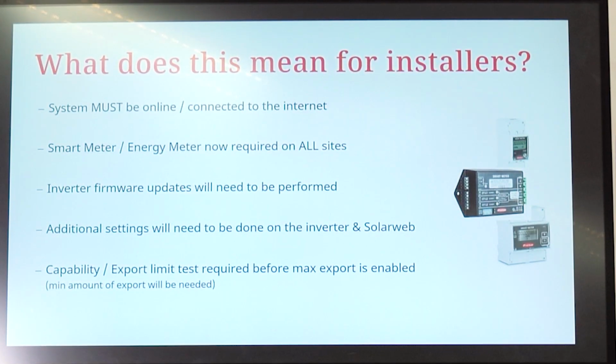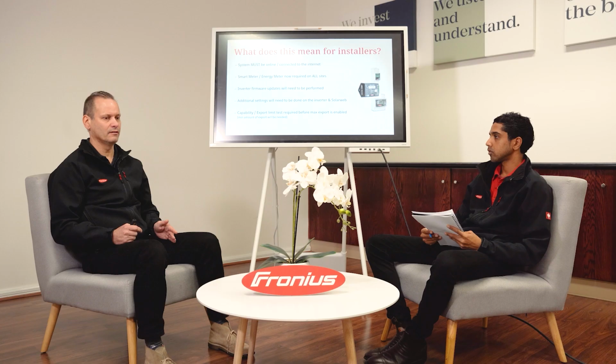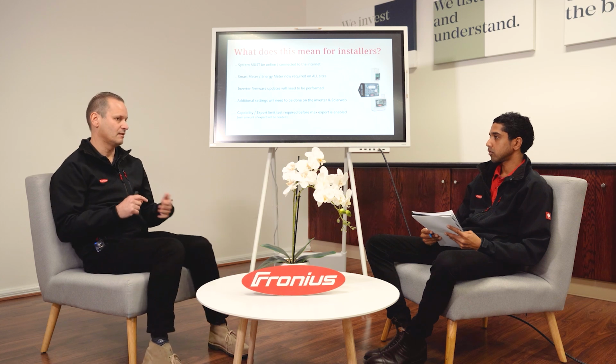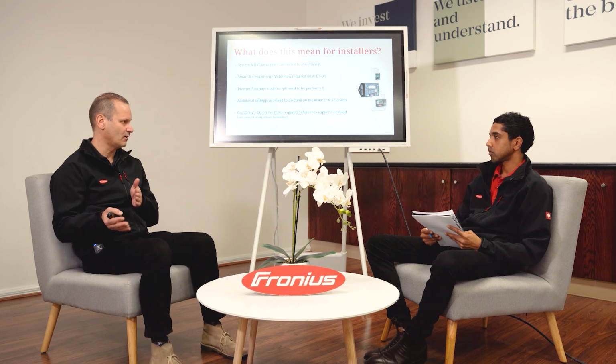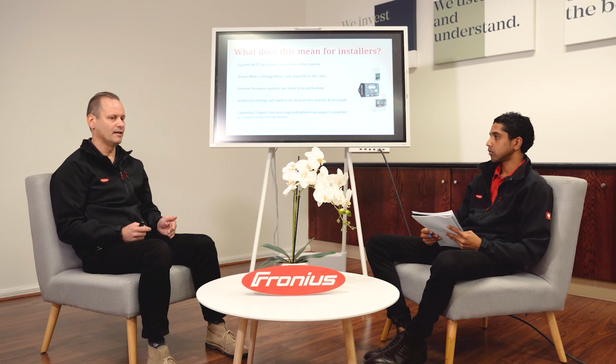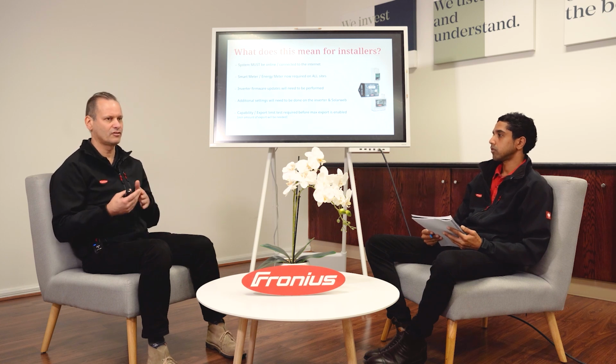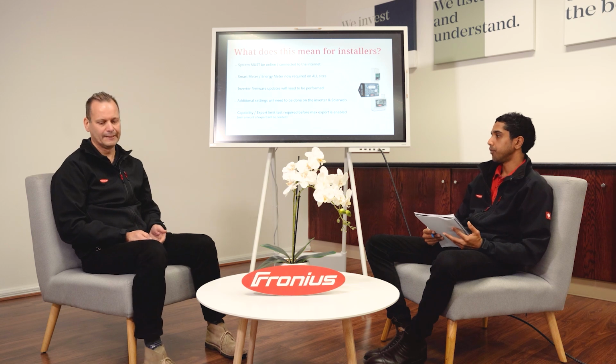The other thing is that from now on, all systems will require a smart meter or energy meter, depending on how you want to put it, like an export meter. The reason for that is, first of all, it needs to be able to pass the capability tests. Secondly, the DNSPs, this is what I've been told, want to prepare for flexible exports going forward. If someone wants to go on to flexible exports and increase their export from their set limit, let's say 5 or 1, whatever they've been issued for that site, then it's a really easy transition. It's just a software change, so there's no hardware needed. That's their future-proofing plan from what I've heard.